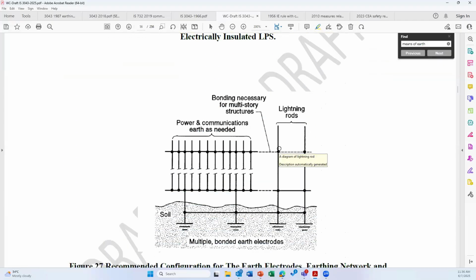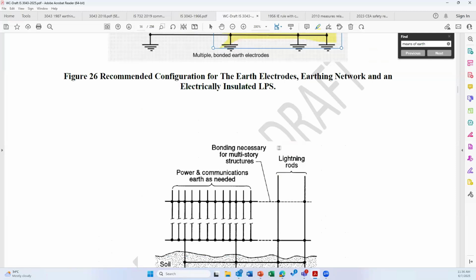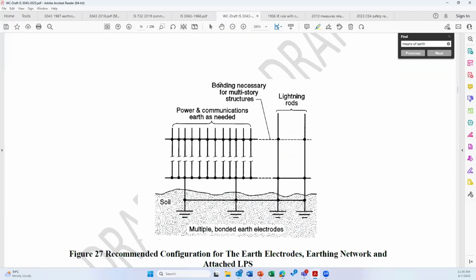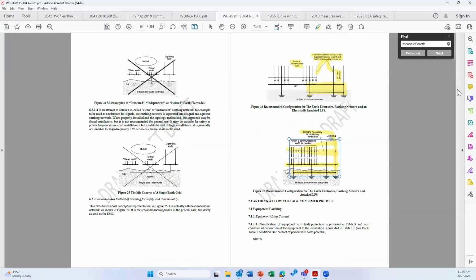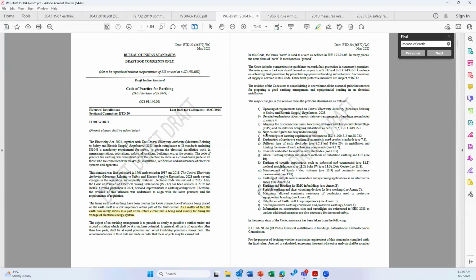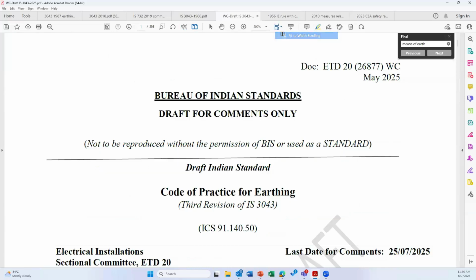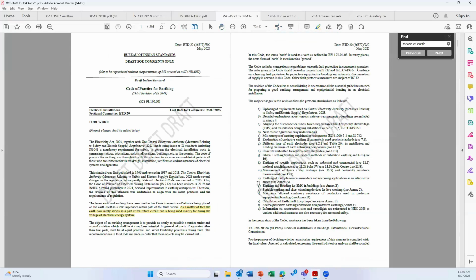Now, for multi-storied buildings, if you cannot maintain the separation distance, then the whole earthing looks like this. You have to bond all the metal parts, including the lightning down conductor, from the top to the bottom of the building. So, many equipotential bonding. The idea is there is no potential difference, so there is no failure. Basically, in the new code of practice, these kinds of misconceptions, which were already there in different standards, are being consolidated and included, which is very good information.